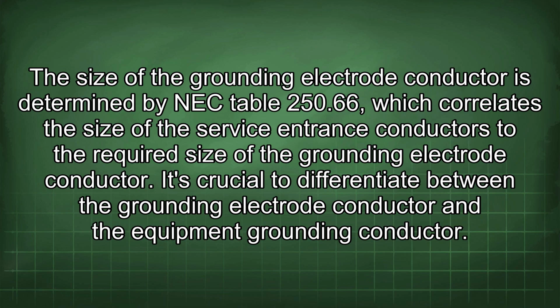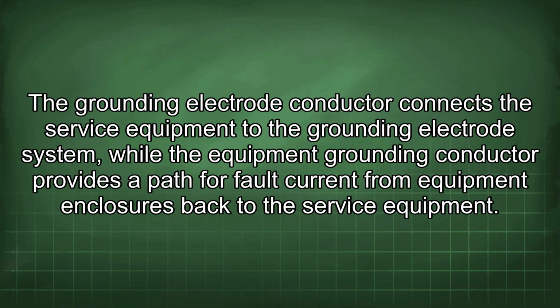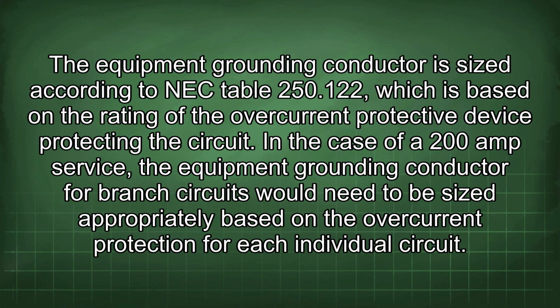It's crucial to differentiate between the grounding electrode conductor and the equipment grounding conductor. The grounding electrode conductor connects the service equipment to the grounding electrode system, while the equipment grounding conductor provides a path for fault current from equipment enclosures back to the service equipment. The equipment grounding conductor is sized according to NEC Table 250.122, which is based on the rating of the overcurrent protective device protecting the circuit. In the case of a 200 amp service, the equipment grounding conductor for branch circuits would need to be sized appropriately based on the overcurrent protection for each individual circuit.